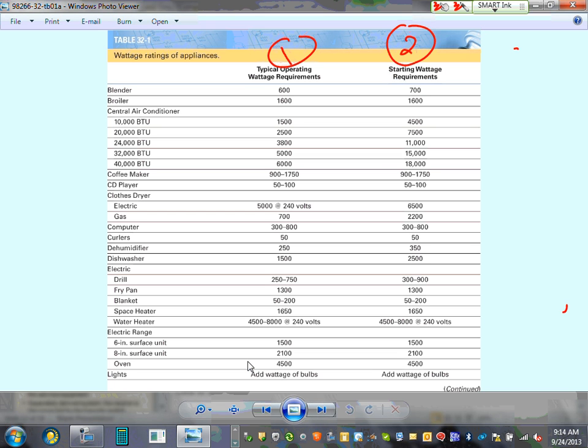I don't think you have a whole lot of control when you're dealing with a dwelling. I guess you can personally, but be aware that if you buy a generator and it keeps tripping on you, make sure to turn certain lights and certain loads off, then start your generator, and then start turning them on one at a time. That's called the starting load.